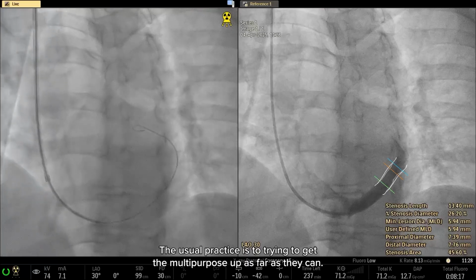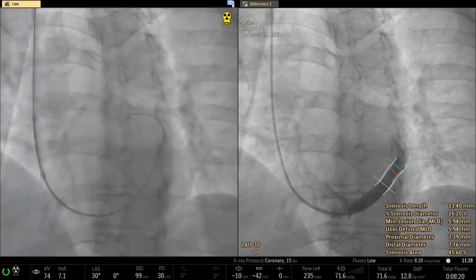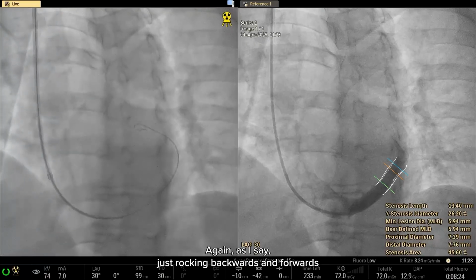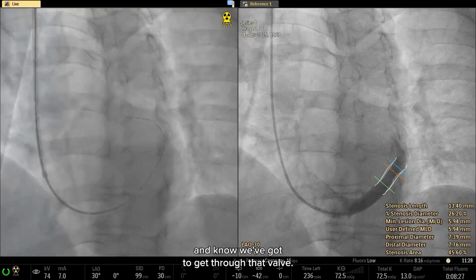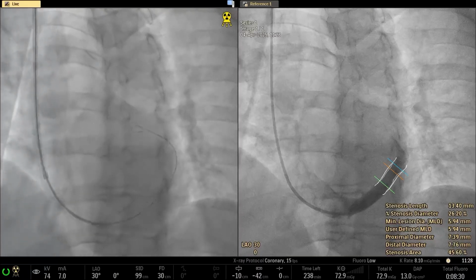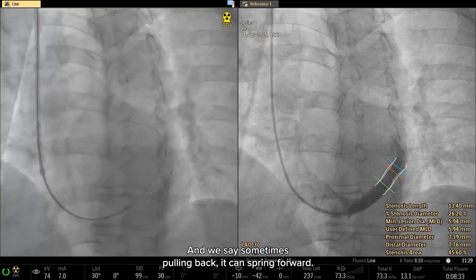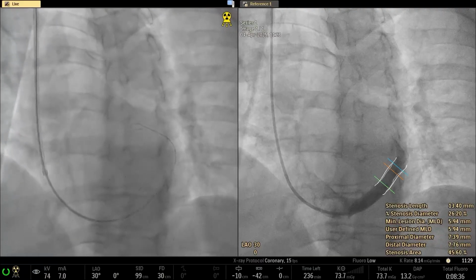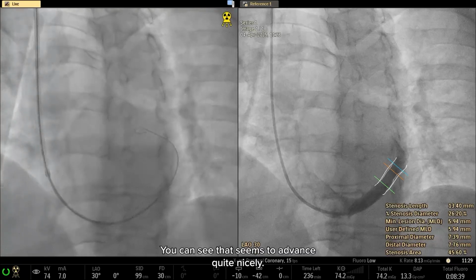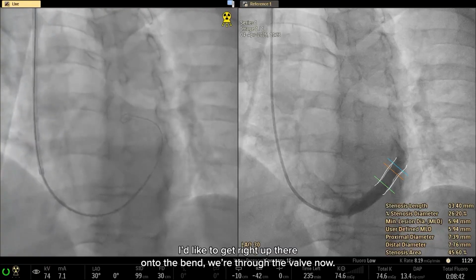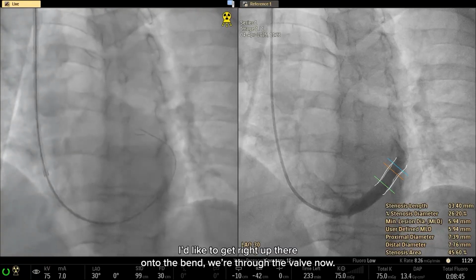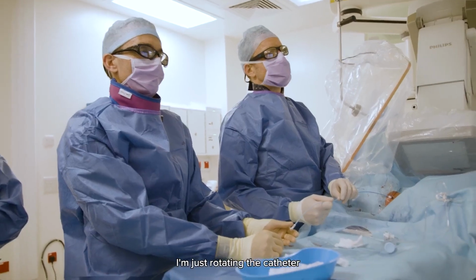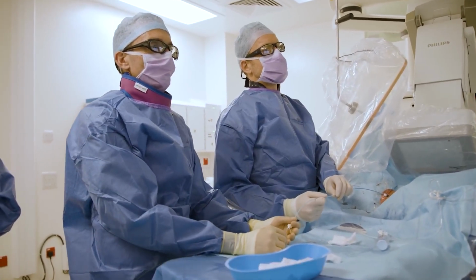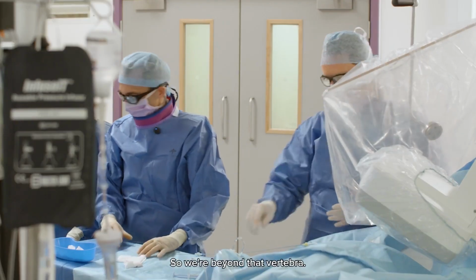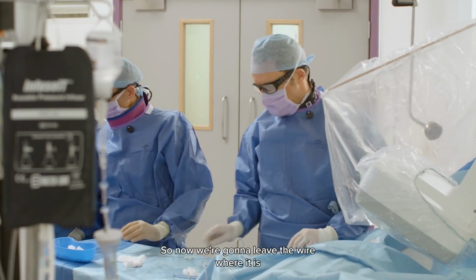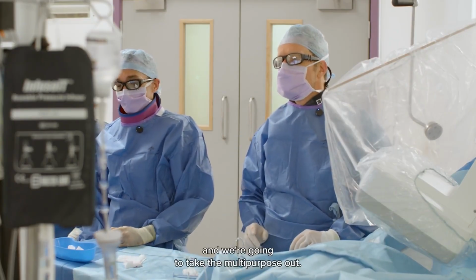The usual practice is to try and get the multi-purpose up as far as I can. Again, as I say, just rocking backwards and forwards. We know we've got to get through that valve. We're just watching the wire. As you say, sometimes pulling back, it can spring forward. It's not a push. You see that seems to advance quite nicely. I'd like to get right up there onto the bend. We're through the valve now. I'm just rotating the catheter backwards and forwards through my fingers. Good, so we're beyond that vertebra. So now we're going to leave the wire where it is, and we're going to take the multi-purpose out.